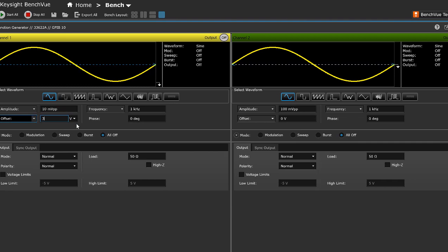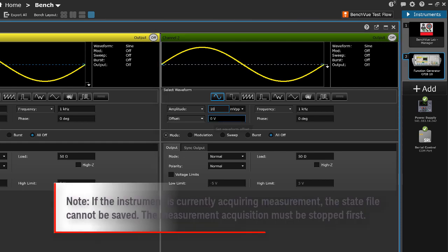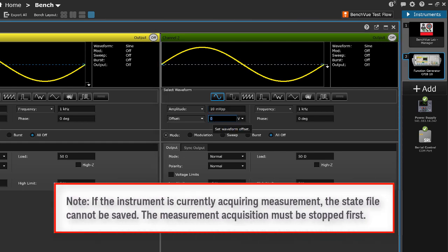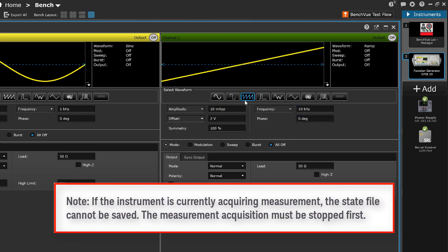You may also set the parameters for channel 2 as well. Please note that if the instrument is currently acquiring measurement, the state file cannot be saved. The measurement acquisition must be stopped first.